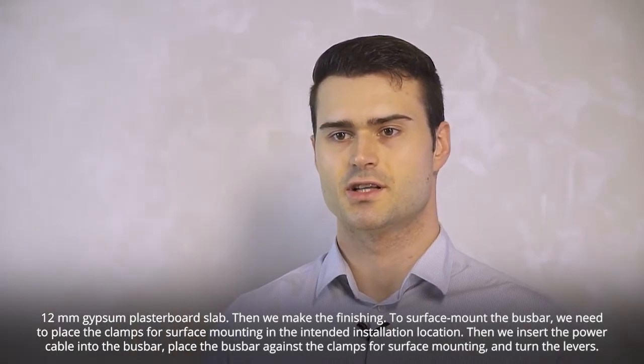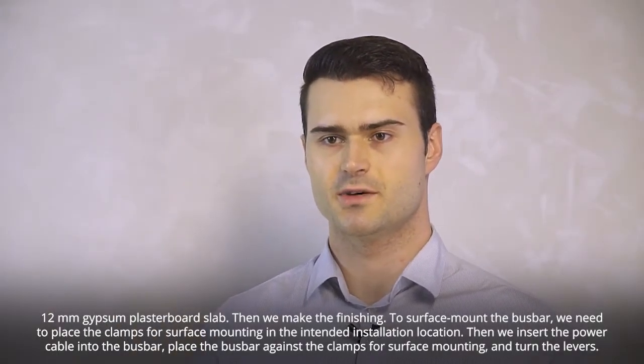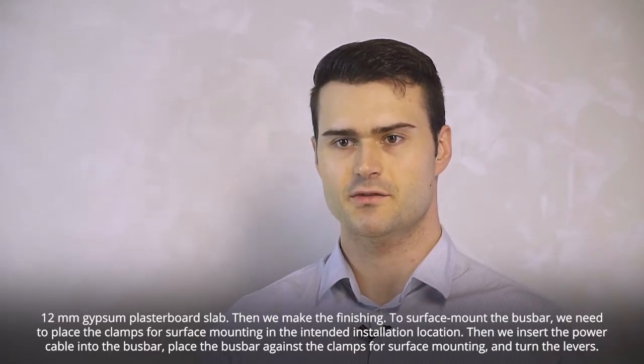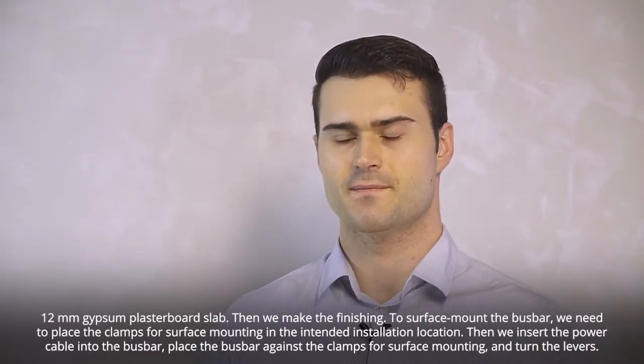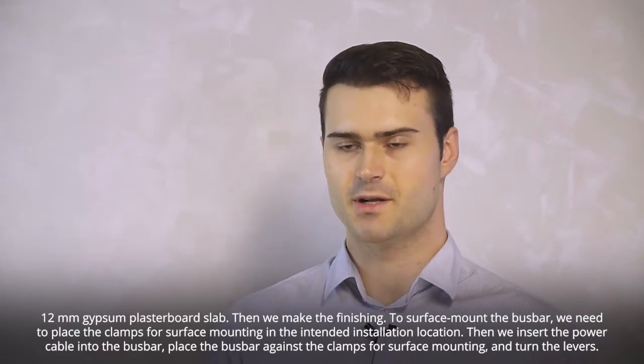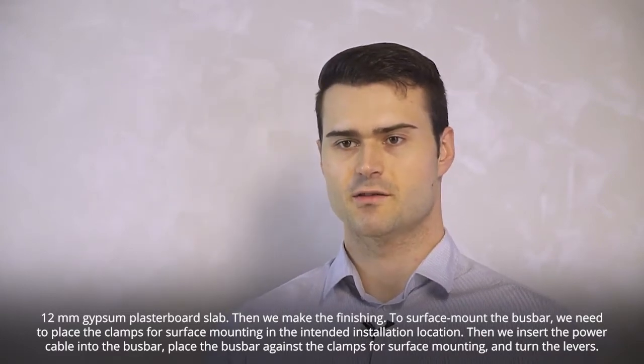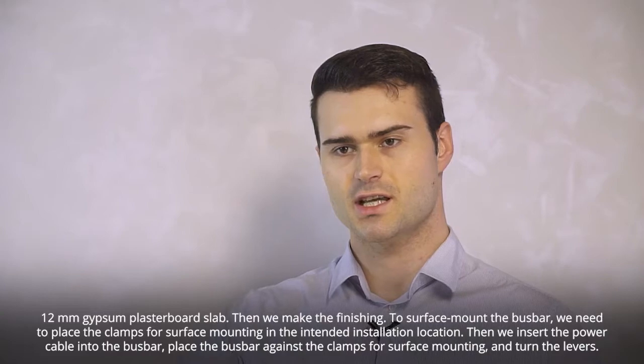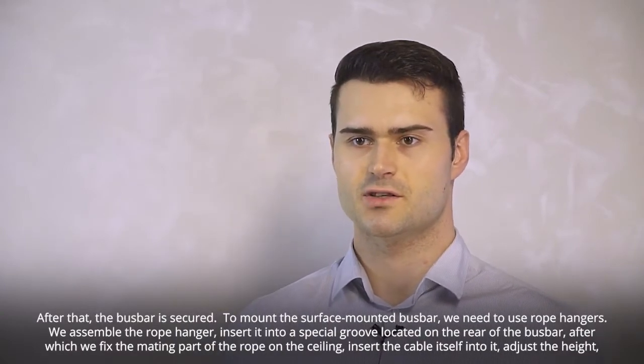To surface mount the busbar, we need to place the clamps for surface mounting in the intended installation location. Then we insert the power cable into the busbar, place the busbar against the clamps for surface mounting, and turn the levers. After that, the busbar is secured.